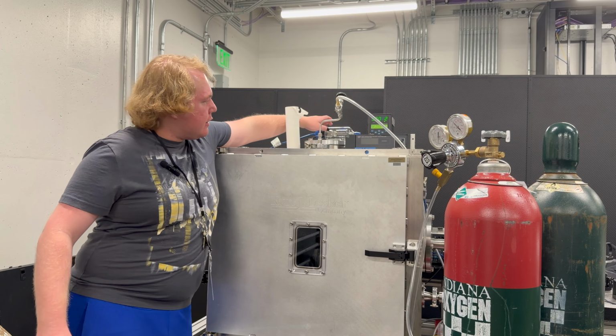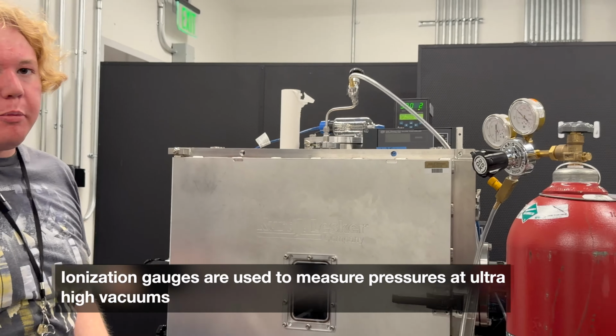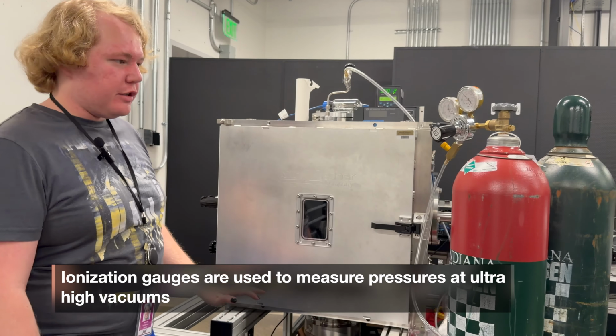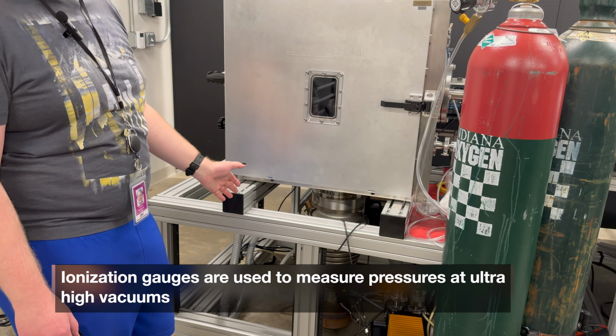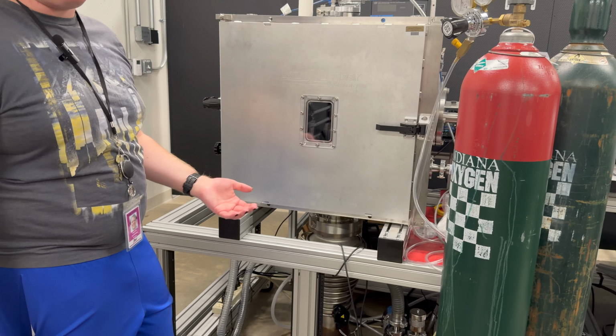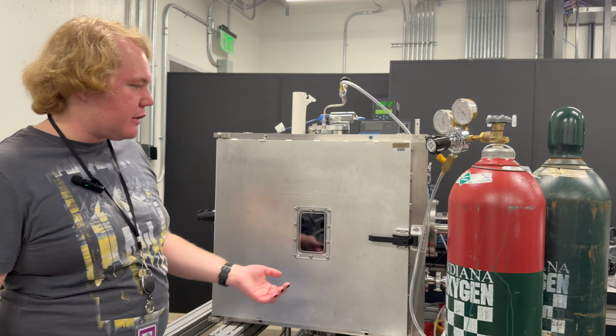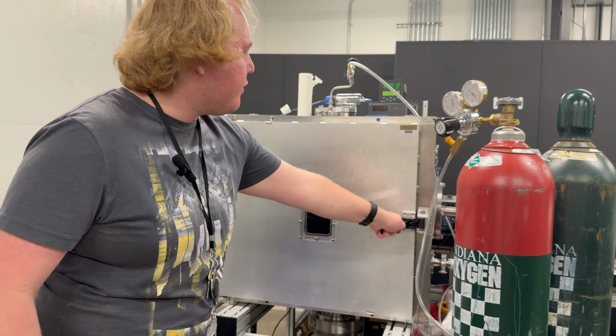As well, back here is the Bayard-Alpert gauge that is connected to the ionization gauge. It only operates when we're using the diffusion pump, which is nominally only here in order to clean up the atmospheric gases that are trapped inside the microwave absorbing panels that we have inside.